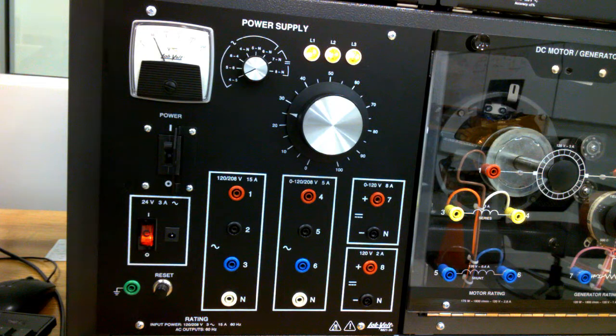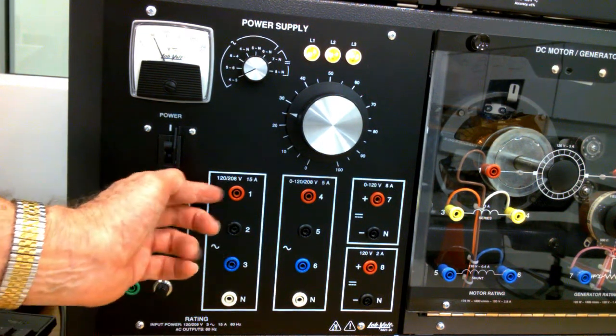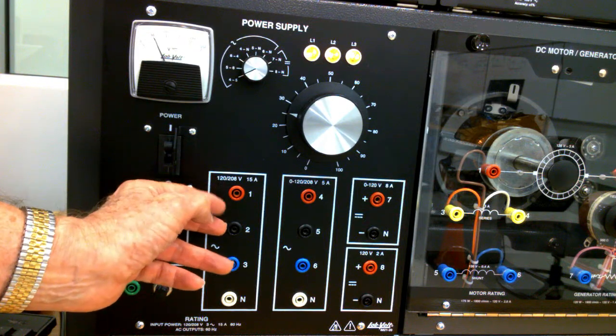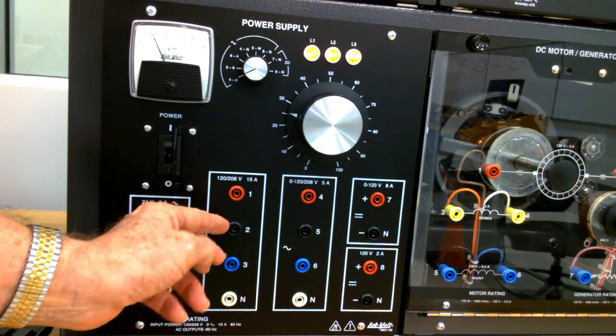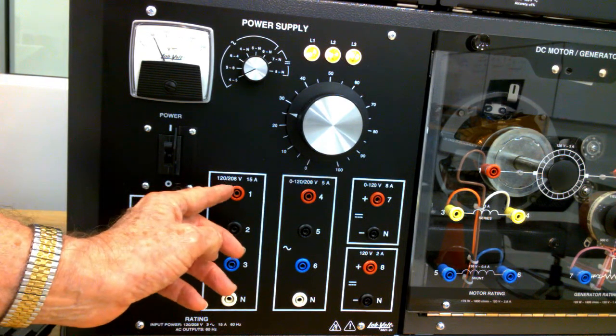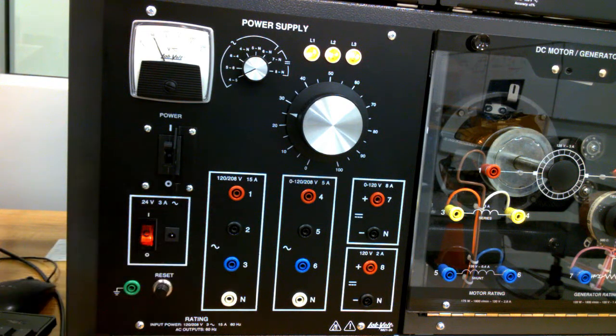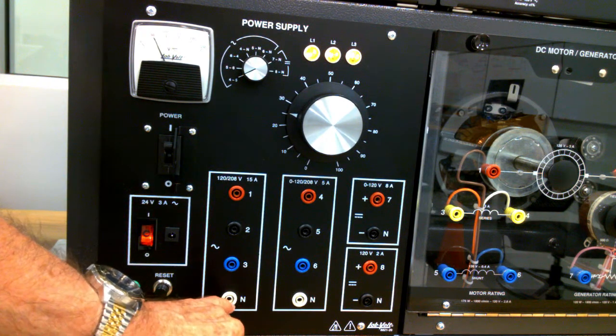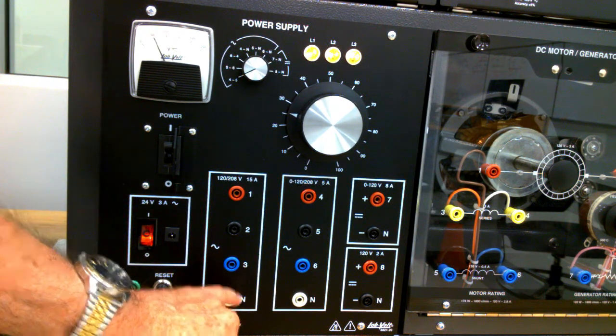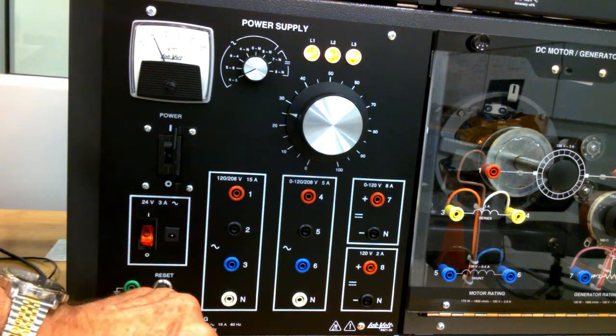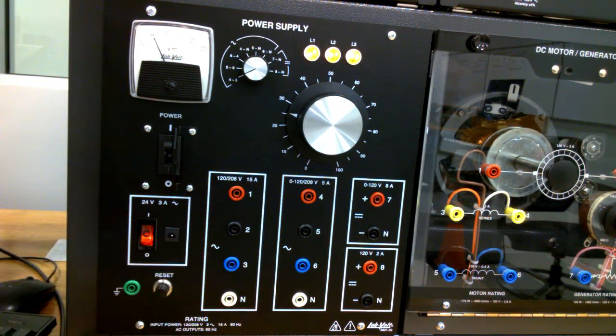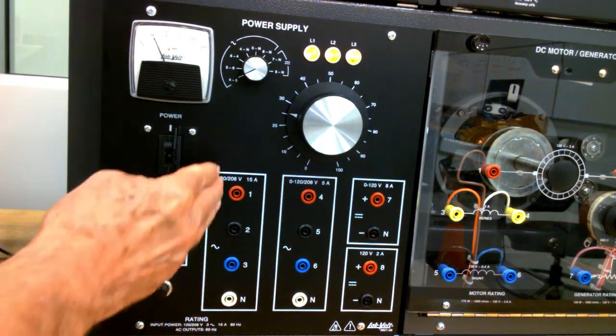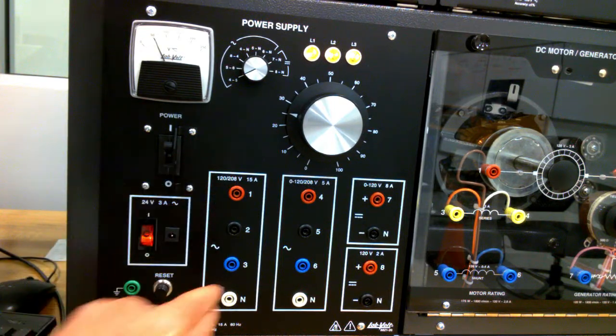white. It is three-phase, so I can use terminal 1 with respect to terminal 2 with respect to terminal 3, and terminal 1 with respect to terminal 3 to get three phases of what we call line voltage. And the neutral, we only have one, but by using it with each one of these, we can get 120 volts. This is a fixed voltage source right here.